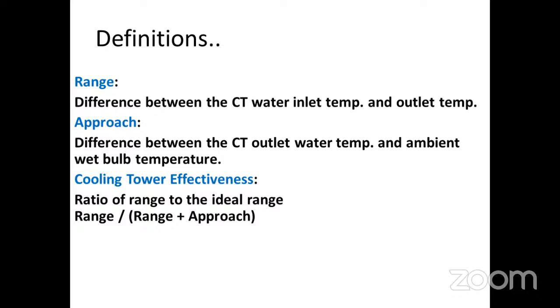Approach is the difference between cooling water outlet temperature and the wet bulb temperature. In ideal case, we can cool the cooling water or hot water to ambient wet bulb temperature. That is theoretical. See this formula as range by range plus approach. When this approach becomes lesser and lesser, what will happen? Both numerator and denominator will approach 1. Yes. Range by range is equal to 1. Yes, sir. Yes, you're right.